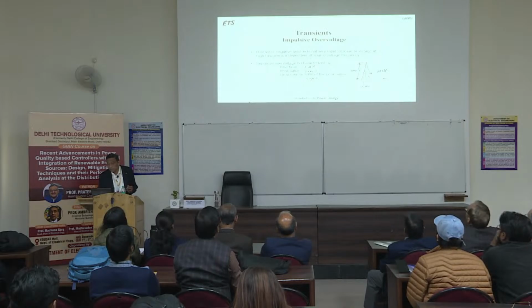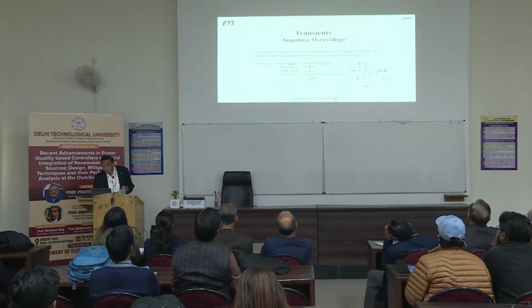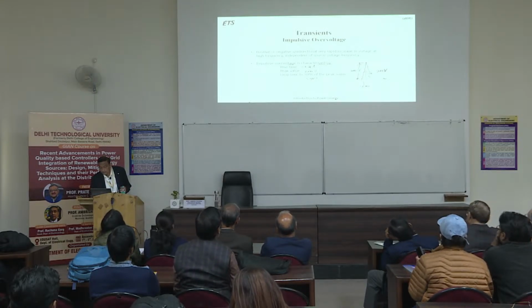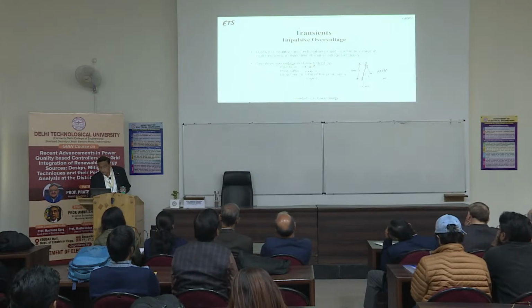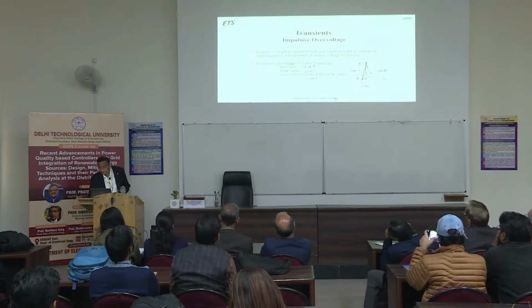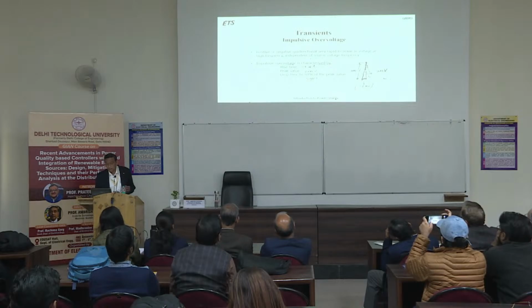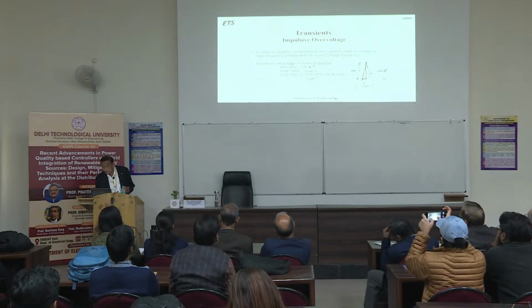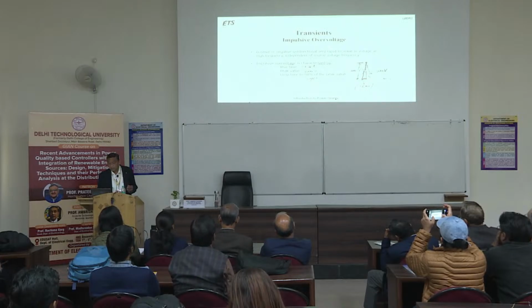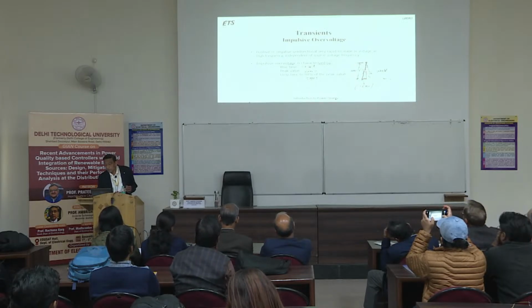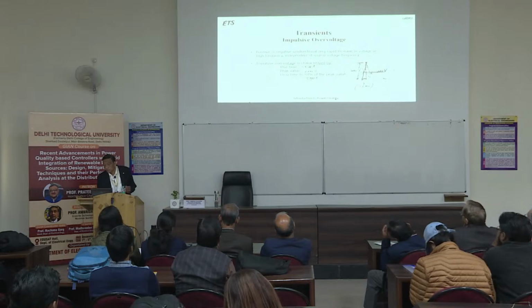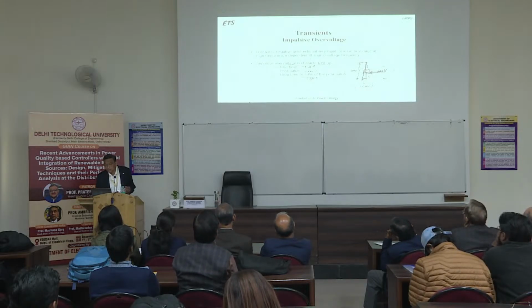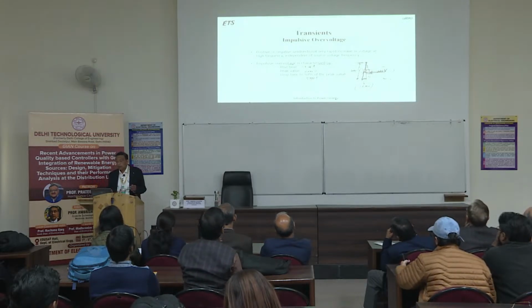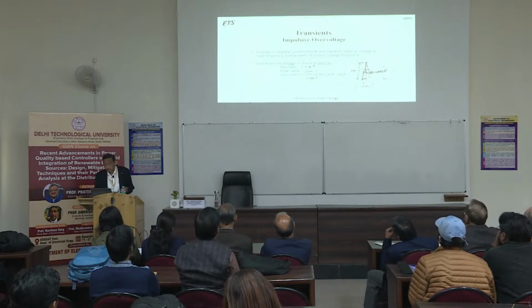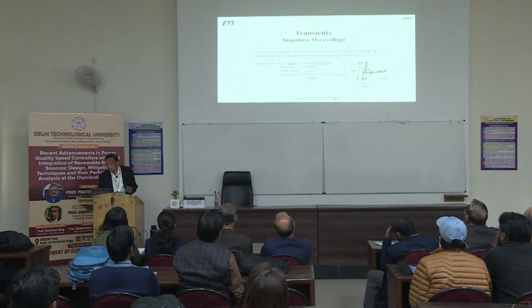Impulsive overvoltage is characterized by rise time. So you see, this is an example, impulsive voltage. The rise time is this, 1.2 microseconds. Peak value, for example, it is just an example, 2000 volts in 1.2 microseconds. And drop time to 50%. 50% means 1000 volts. So here you can say this is the drop time up to 50% of the peak value, maybe 50 microseconds or something, that depends.